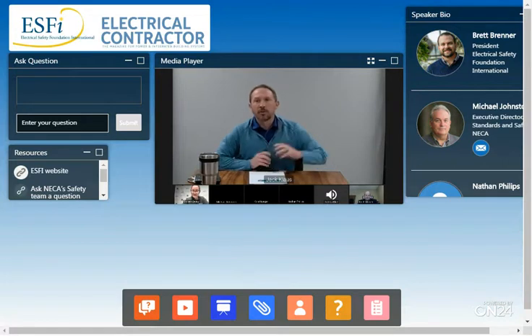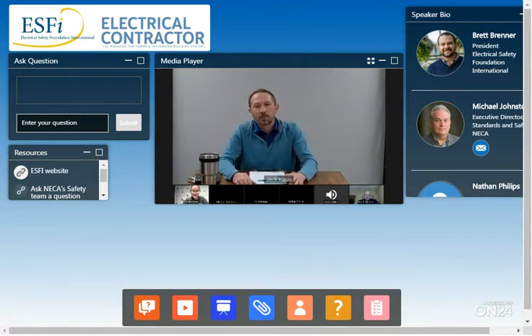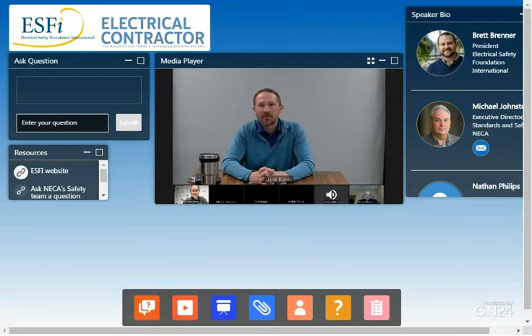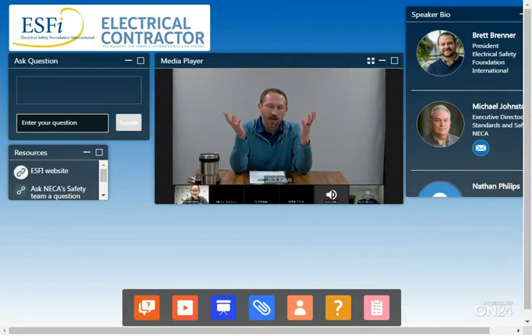It's really expensive to track transients through power quality monitors. You're looking at between 10 to 20 grand per device that you'd put throughout your facility, but that's only half the battle. You're going to see the transients, you can go through and read the trilogy at IEEE or thousands of other documents to see if they exist, but then you have to connect that to your failures.